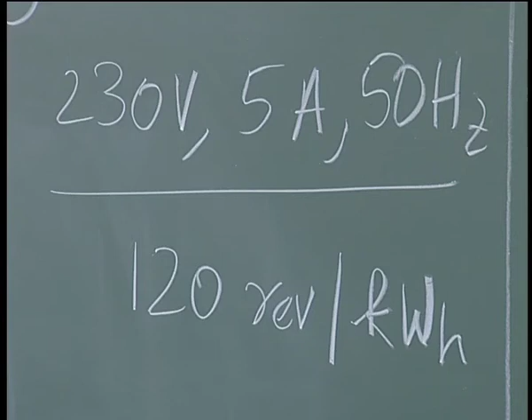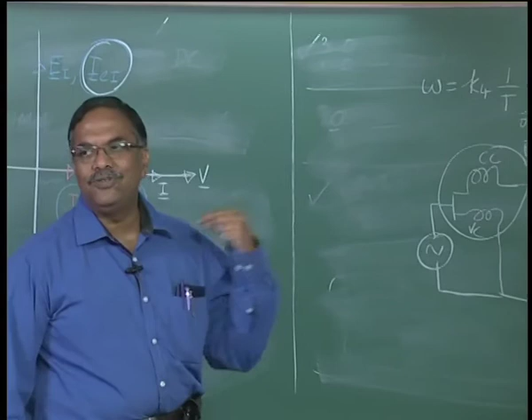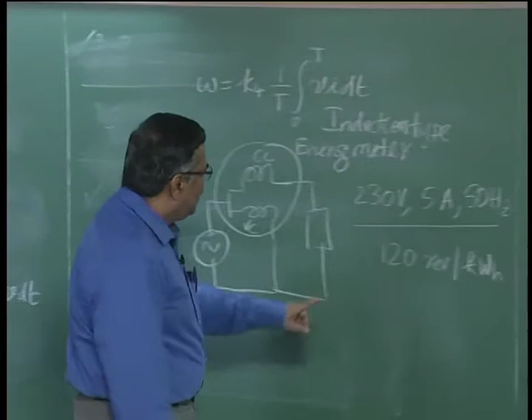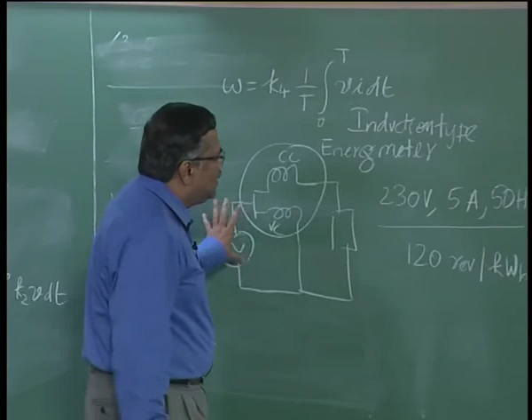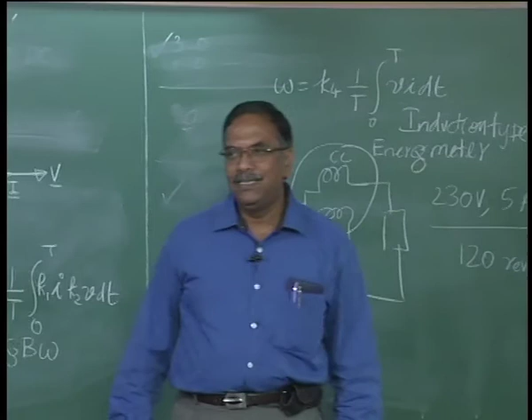If I now connect this meter and draw 1000 watts, 1 kilowatt, for 1 hour, it will run 120 revolutions of the disc, since the number of revolutions is proportional to the power. So a typical specification for an energy meter is 230 volts, 5 amperes, 50 hertz, 120 revolutions per kilowatt hour.